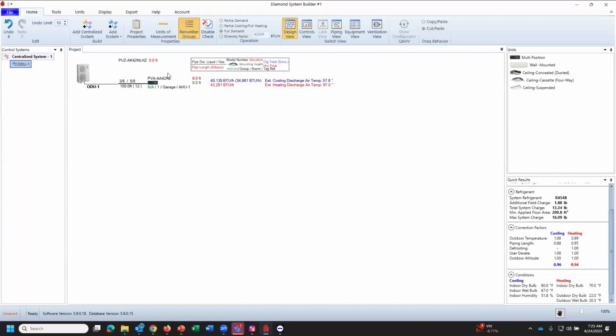A few of the other numbers that I definitely want people to understand here, especially whenever we're dealing with ducted systems: we occasionally see people come back in saying it's not performing the way that I expect, having customers wonder whether it's the system that is derating, or if they've got something going on with their installation, or if they have an incorrect charge. One of the things we get into is that you can actually calculate the BTU output relatively easily, and come back in here, build your system in DSB and check to see if you're putting out what the system is expected to do. It winds up being one of those tools that does come in handy in the field.